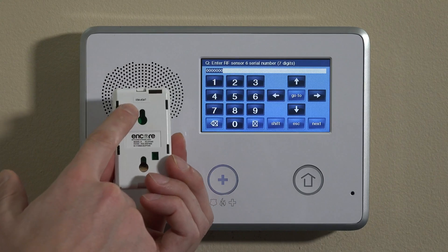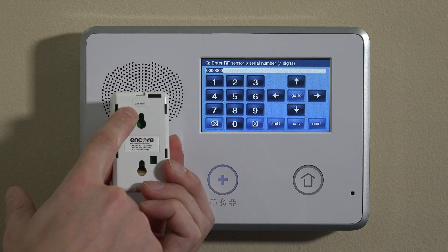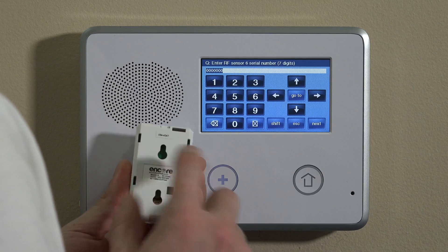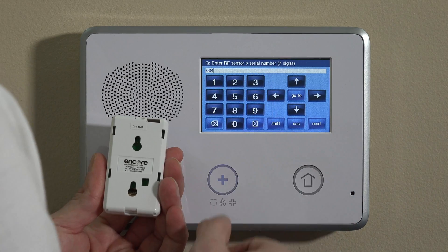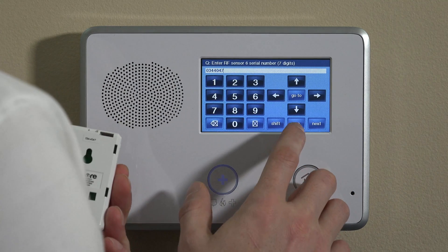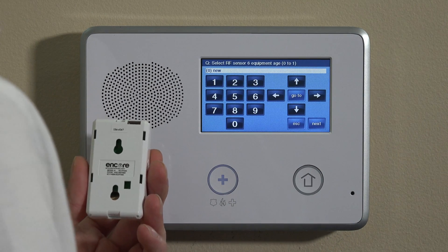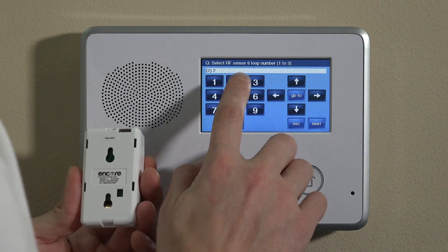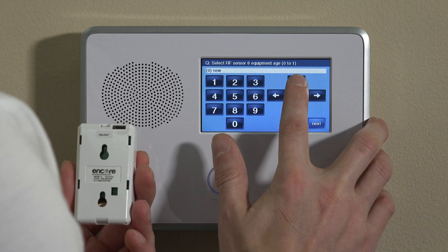There are two ways to enter the serial number, as I mentioned earlier. You can take the 7-digit serial number from the sticker on the back of the unit, or there's a 7-digit serial number listed on the inside of the tamper cover if you've already wall-mounted or ceiling-mounted it. The third option is to auto-enroll it. For manual entry, you would just enter the 7-digit number — for example, 0344047 — hit the down key, set equipment age to new, then enter loop number 2 and keep moving down.